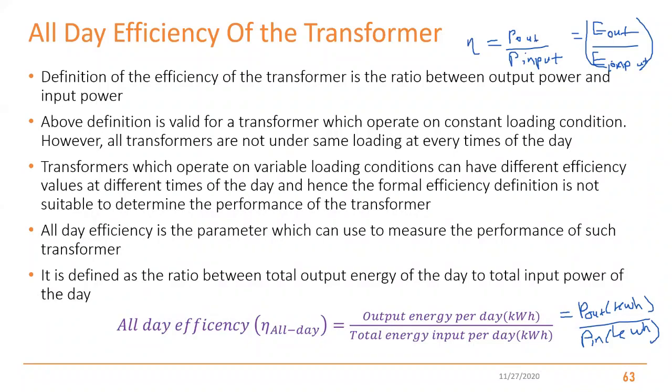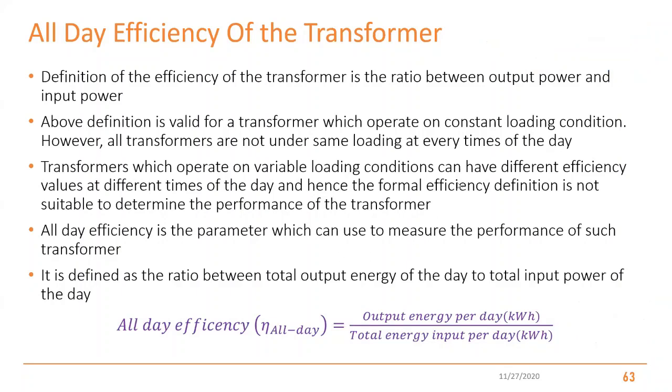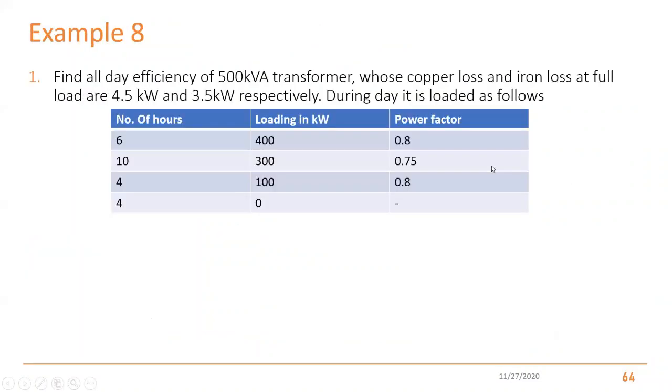So this is not applicable for every transformer. For some transformers, they only have a full load for a certain time, and then they run at no load. Therefore, to measure the efficiency of that kind of transformer, we need to use this kind of method. Otherwise, it is not fair to use the actual definition of the efficiency. So with that, you should be able to calculate the efficiency related to that also.